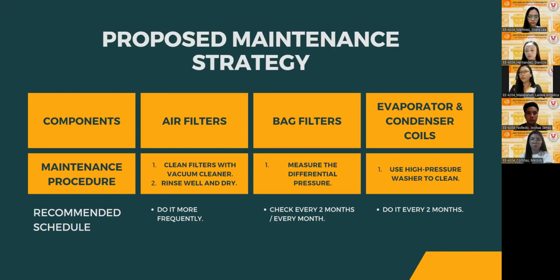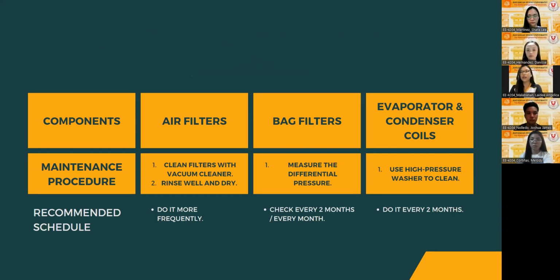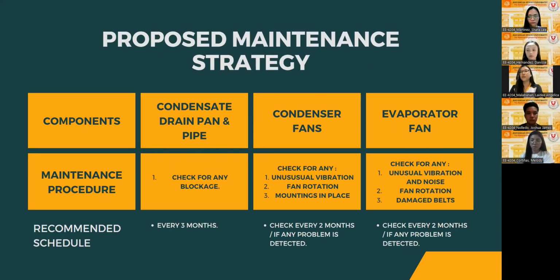For the bag filters, for the maintenance procedure, measure the differential pressure across the bag filters. If pressure exceeds 1.2, replace the filters immediately. For the recommended schedule, check every 2 months. If the environment is dusty, check every month. For the evaporator and condenser coils, use a high-pressure washer to clean and remove any dirt that is clogging the coils. And it should be checked every 2 months, more frequently if the environment is dusty. Next, for the condensate drain pan and pipe, check for any blockage and clean the drain pan. And it should be done after every 3 months.